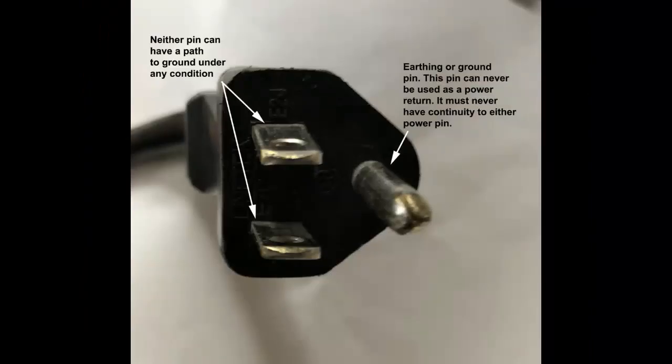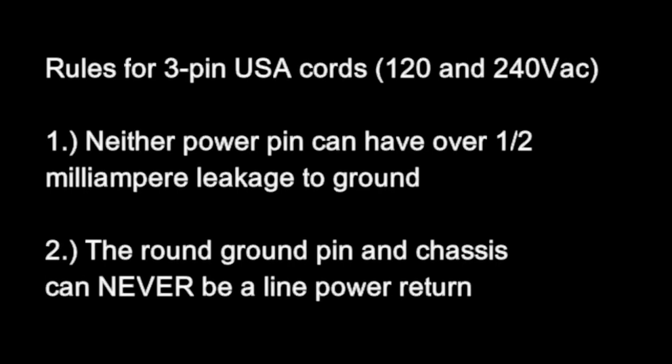Once again, the United States rules for 120 or 240 volt three wire cords are that neither power pin can have a path to the chassis, and the round pin cannot ever be used as a power return.